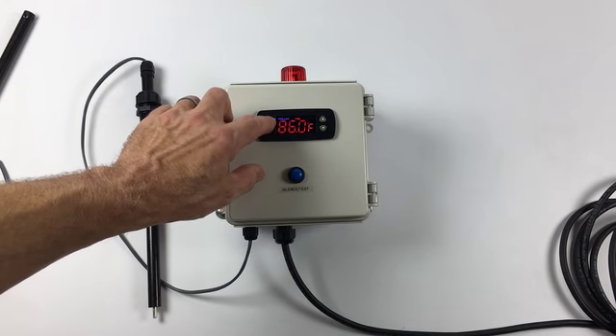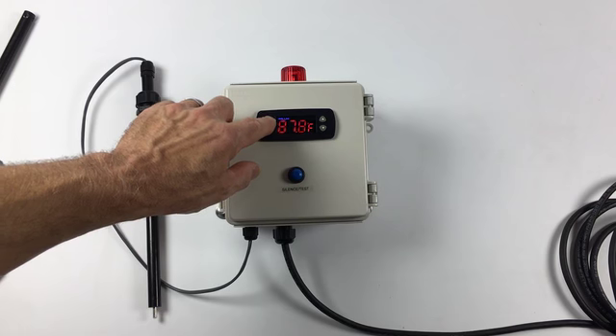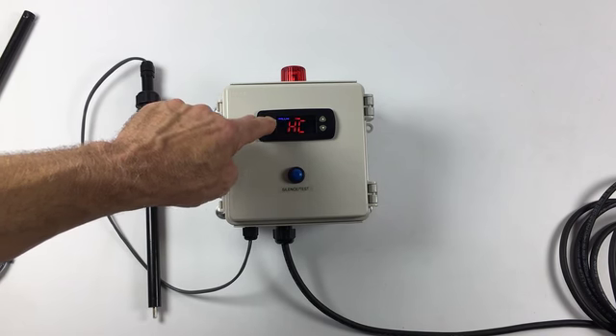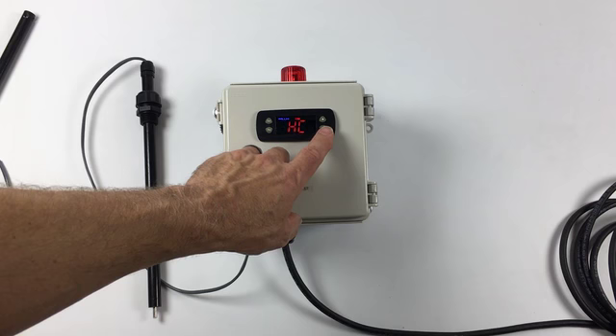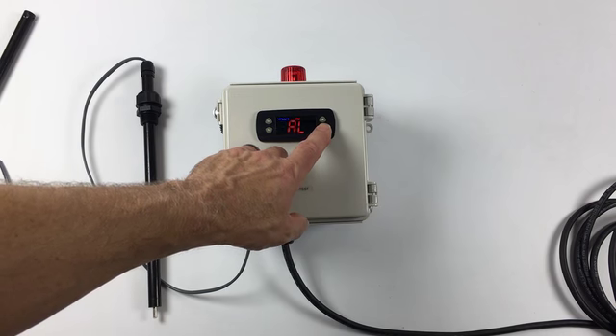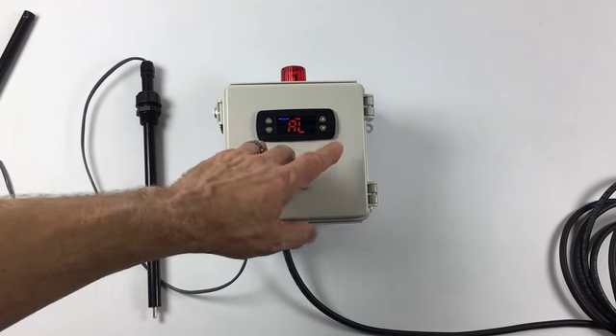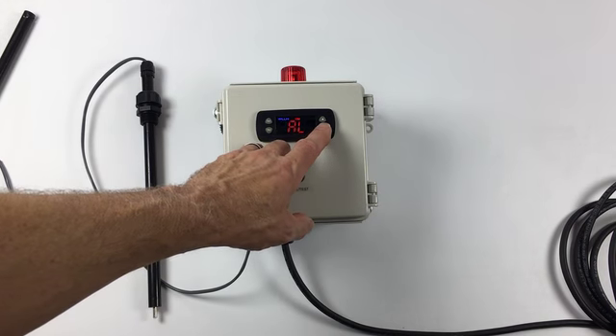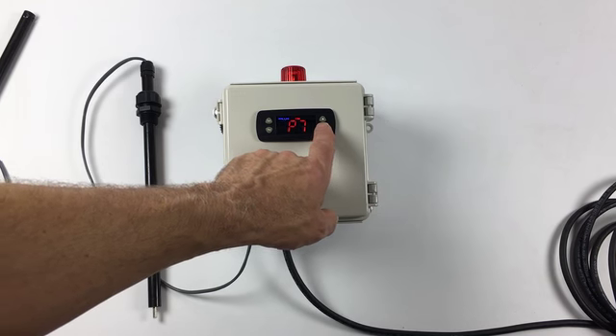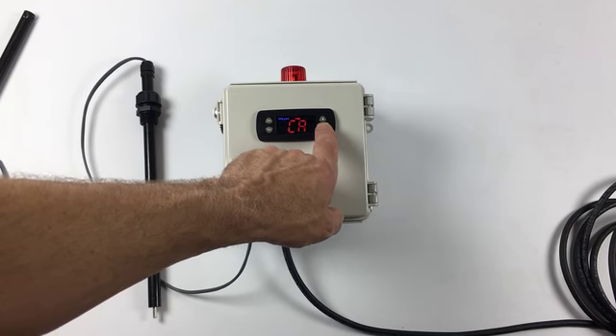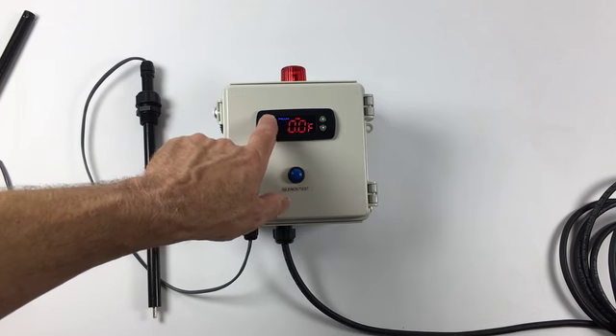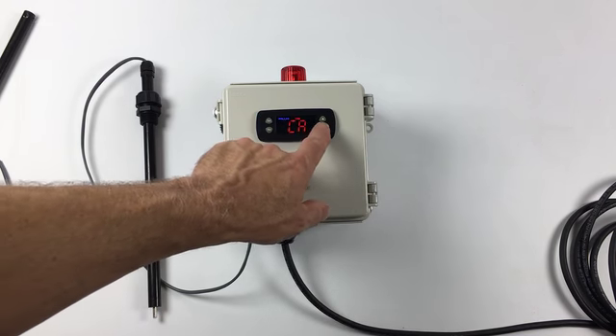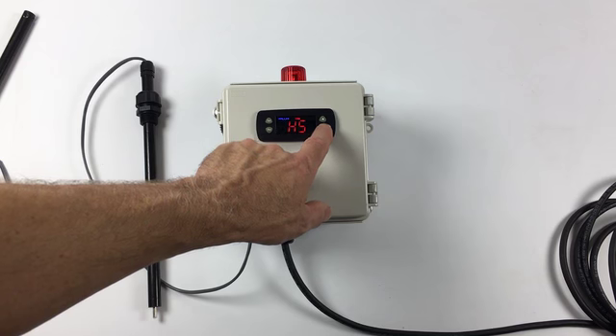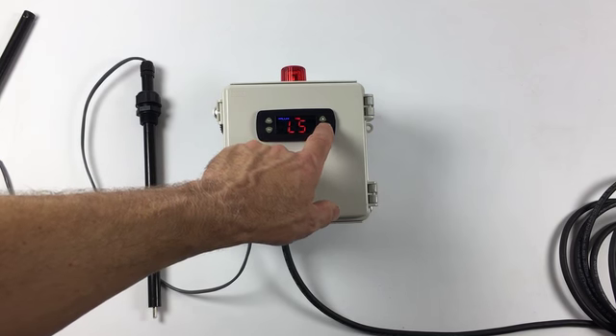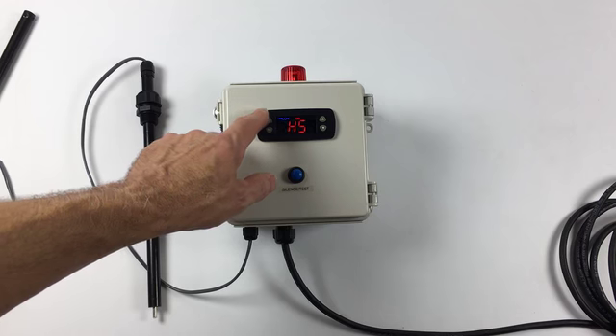I'll step through a couple of the others. 1, 2, 3. So that's heating and cooling mode, but we're not using this as a temperature controller. There's the low alarm set point. It gives you the same range on the low side. We already talked about the high. This is just a time delay, which we don't need. It's already built in. That's the calibration. You can set it for some offset. And here we have the upper and lower set point, which we may use.